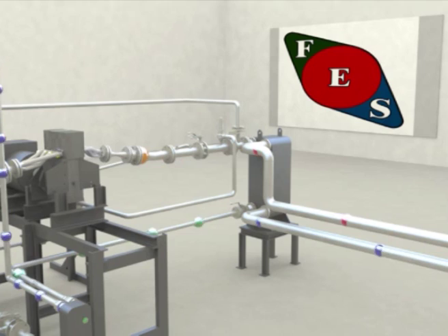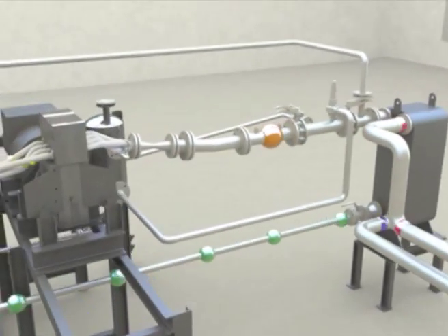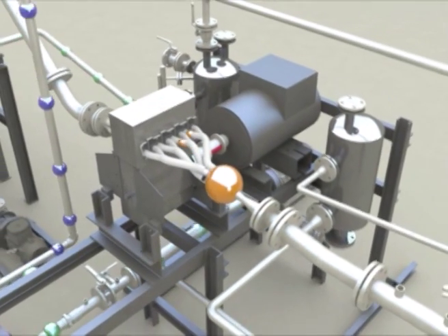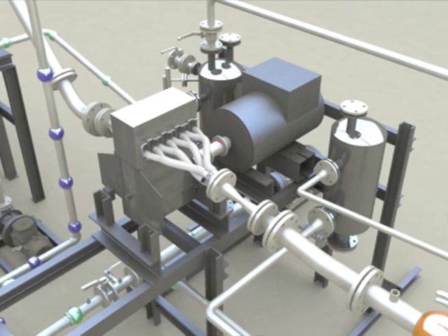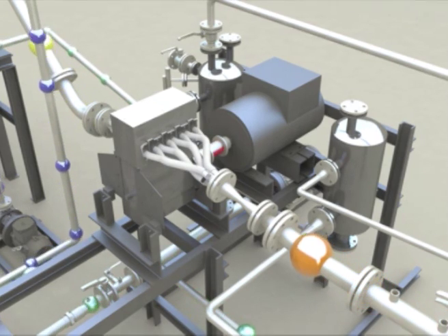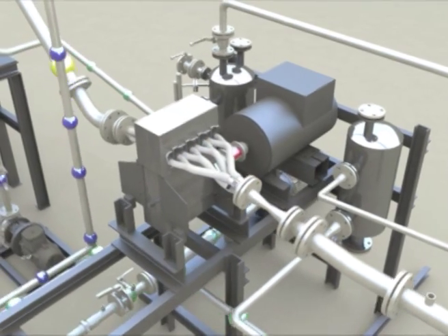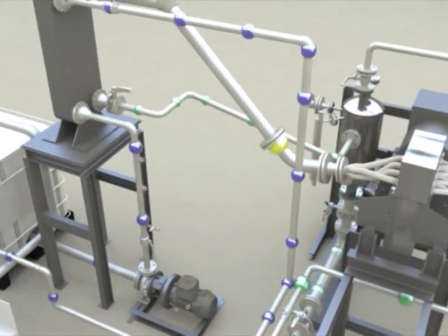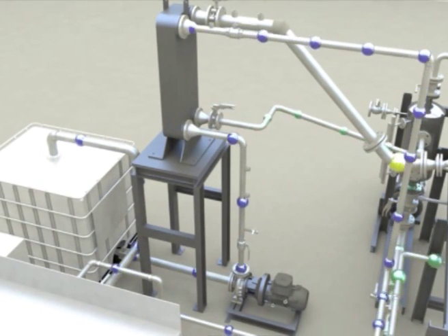The thermal energy is transferred to the fluid engine system via a heat exchanger, referred to as the vaporizer. In the vaporizer, refrigerant is boiled and the resultant pressurized vapor, shown in orange, is supplied to the engine. Work, or energy, is extracted from the pressurized vapor by the engine, producing electricity via the coupled generator. The vapor, in yellow, upon discharge from the engine, has reduced pressure and temperature, but further work must be done on it by the second heat exchanger, or condenser.